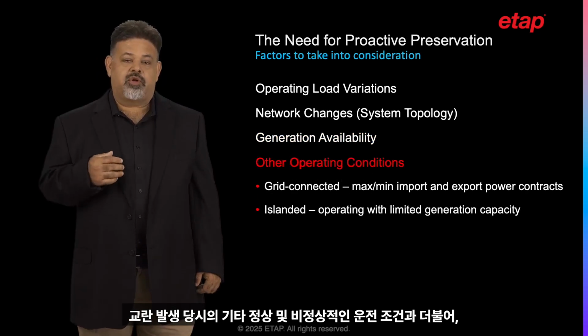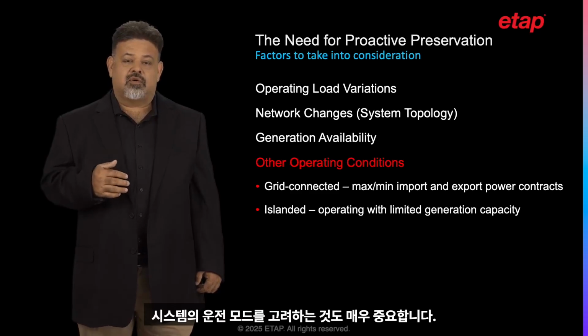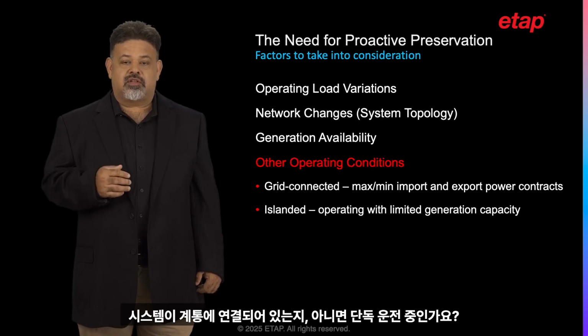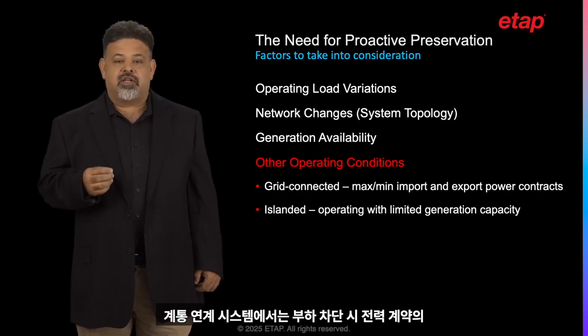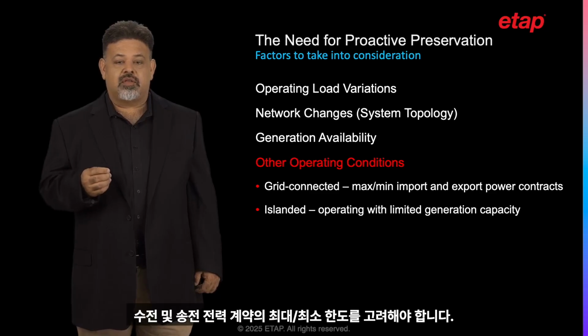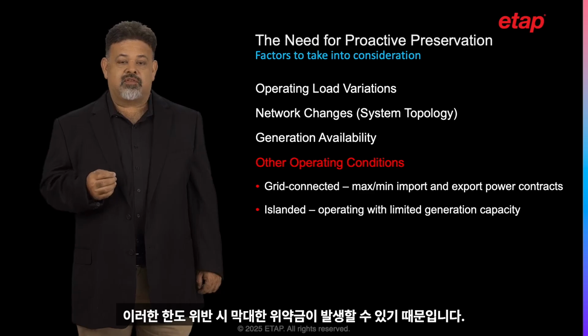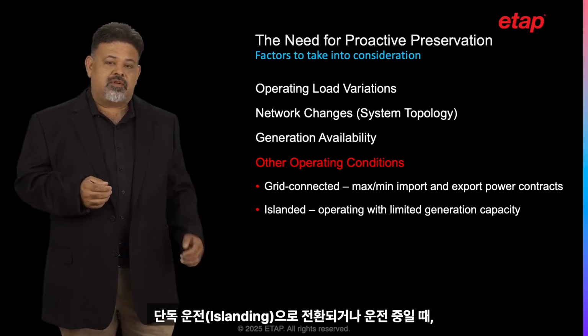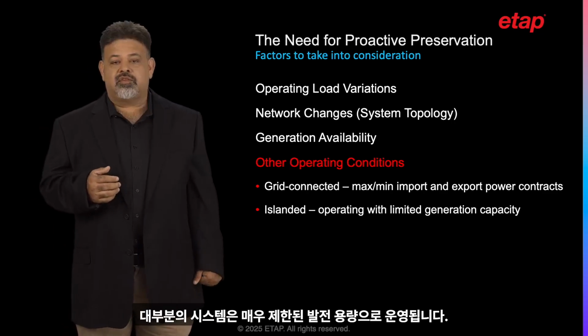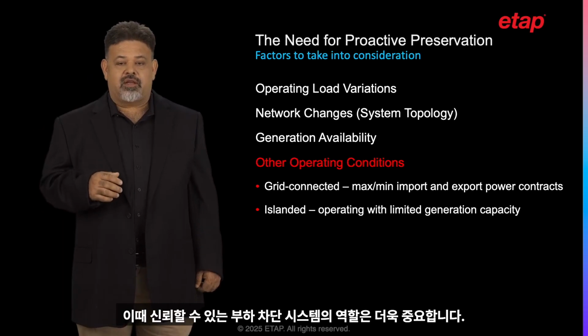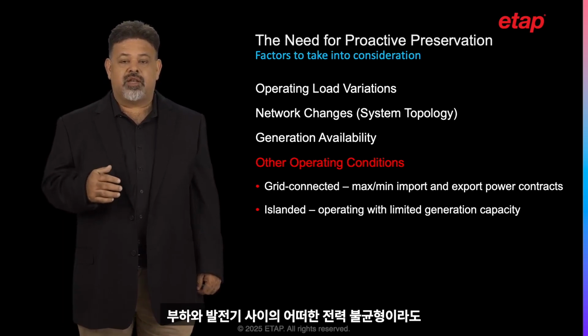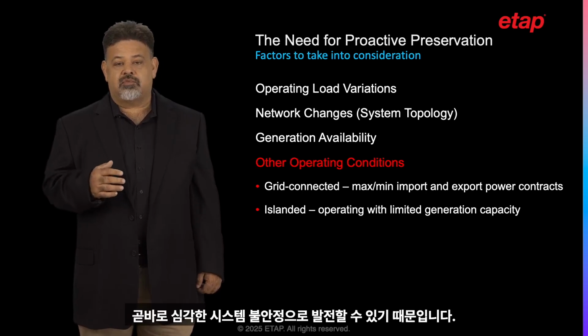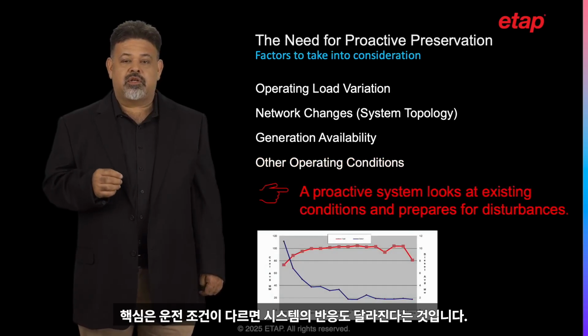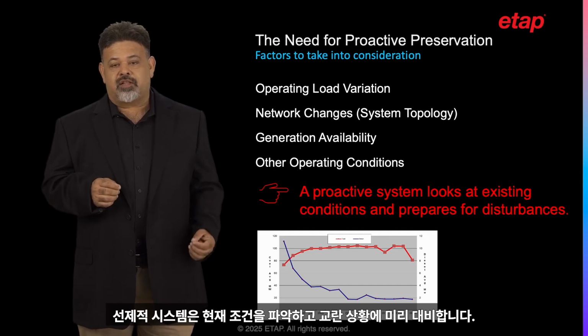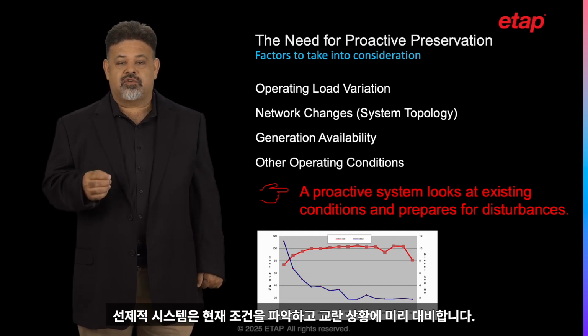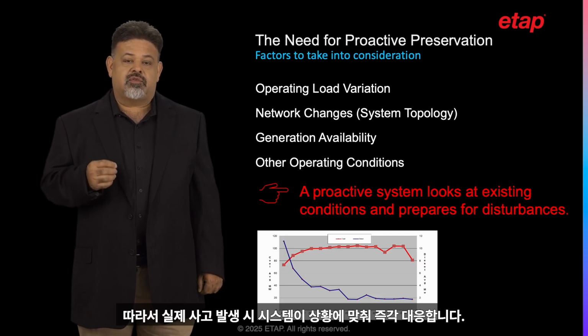Other normal and abnormal operating conditions. At the time of the disturbance, it is also important to consider the operating mode. Is the system connected to the grid or is it islanded? With an interconnected system, the load shedding system needs to consider max and min import and export power contracts, as violating such limits can cause large penalties. After islanding or when operating islanded, most of the time the system is operating with limited generation capacity. A reliable load shedding system is even more critical, as any imbalance of load and generation can develop into an unstable system. The bottom line is that with different operating conditions, you get a different response. A proactive system will look at the existing conditions and prepare for disturbance events, so when they happen, the system is ready to respond accordingly.